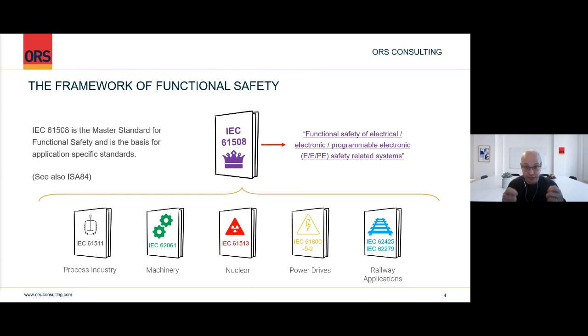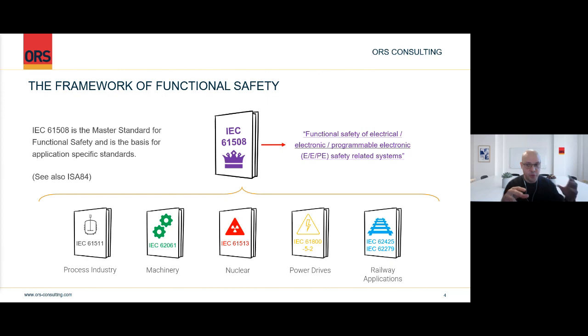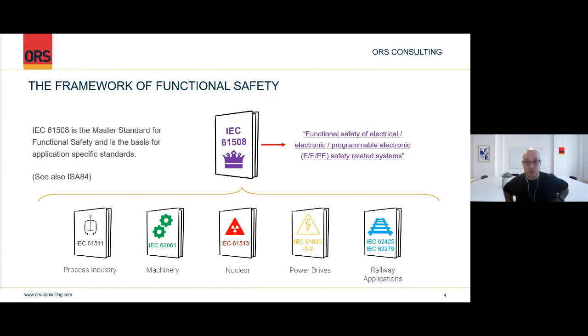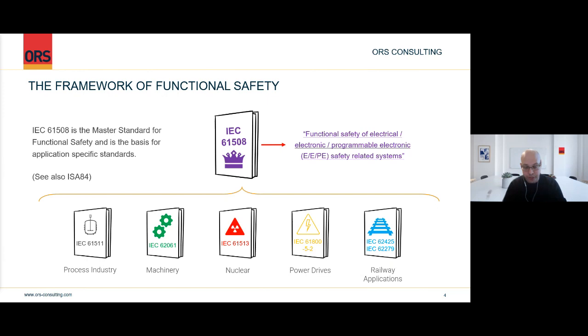IEC 61508 is the master standard for functional safety. Whenever you have a question about functional safety, you go to the standard or to someone who knows a lot about it. Below IEC 61508 exists many application-specific standards. If you work in the process industry, you've heard of IEC 61511, which is the application of 61508 to the process industry. There are also standards for machinery, nuclear plants, power drives, railway applications, and the automotive industry. They all define how functional safety is applied to their specific industries, and therefore how SIL is defined for each of them.